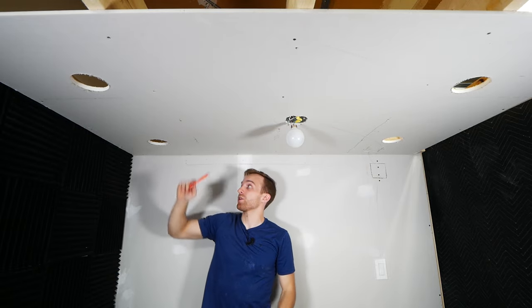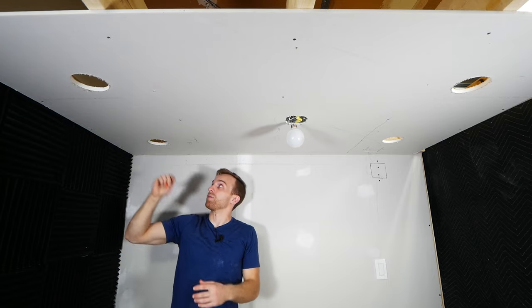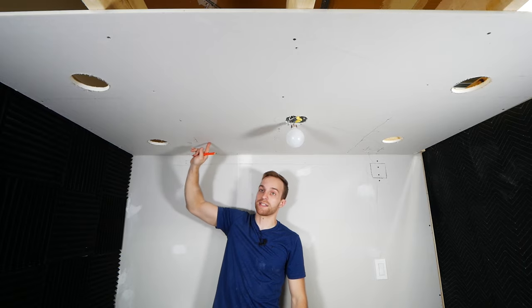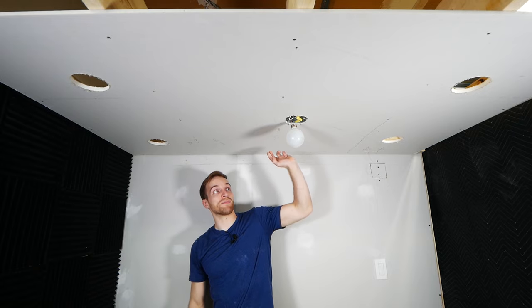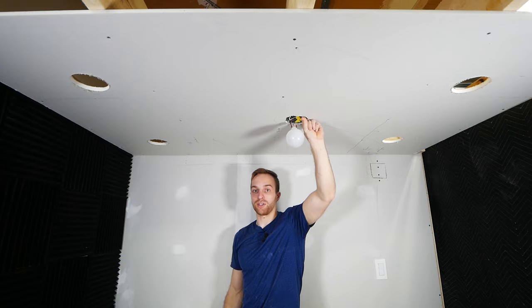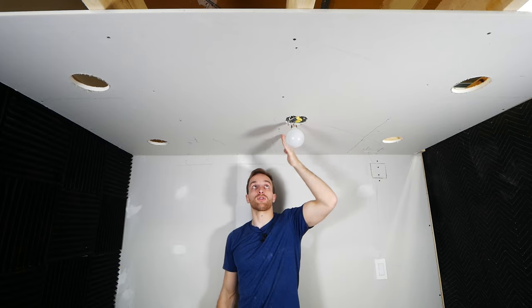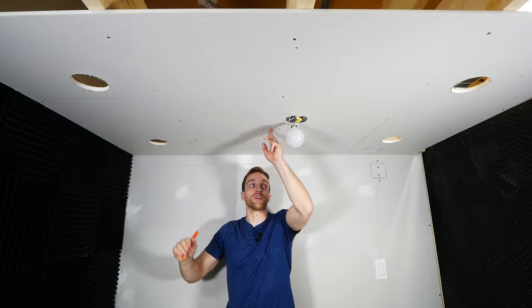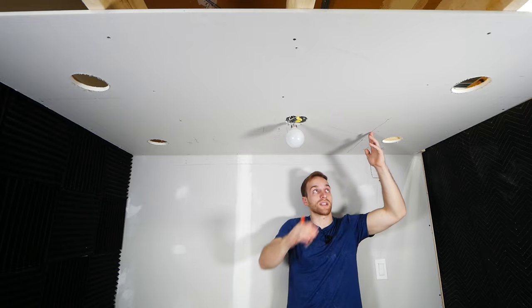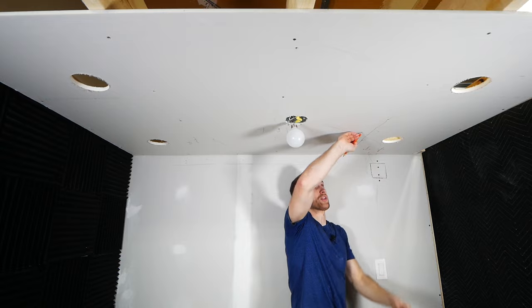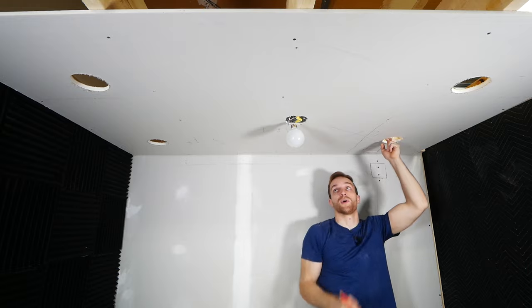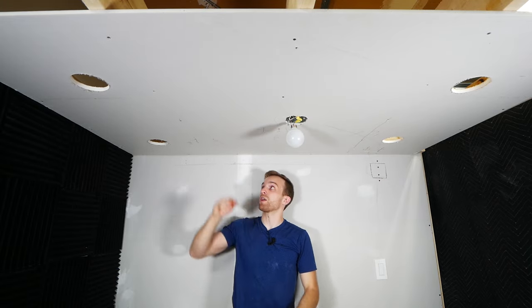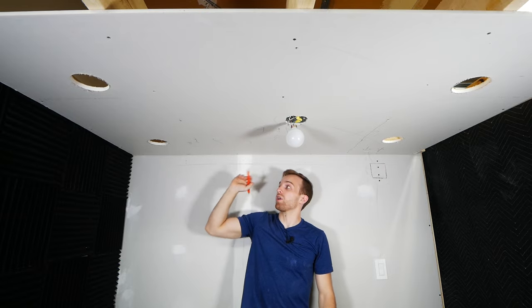If I'm looking at joist A here, I can see this side of it. Okay? We are good. I can see it through this hole. I cannot see this side, however. That is a problem. If we're looking at joist B, I can see this side of it through our light fixture. If I were to take this box out, I can get a good look at this side and see that we are good. But once again, no good. If I were to look at this joist, once again, we can see this side through our octagon box. We are good. And this side, I can see through this hole and know that we are good. So, in this situation, all I have to do is make one hole, and that's going to be in this joist space.